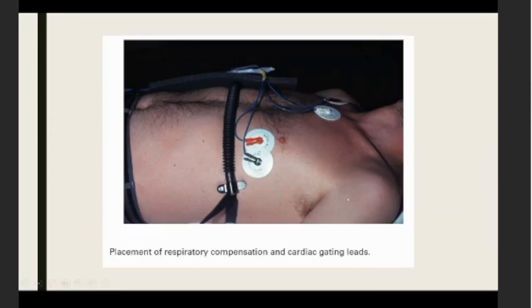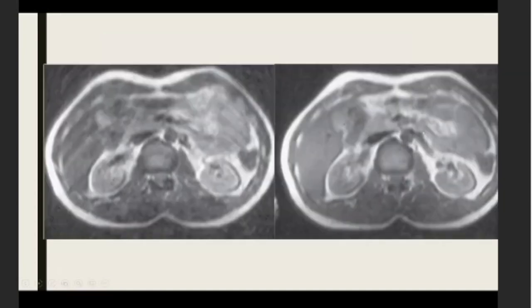As shown in this picture, the trigger line in black is used to define the breath cycle, and here are the cardiac gating leads. On the left side is the image taken without respiratory gating or compensation technique — the ghosting artifact is visible all over the image. On the right side, we used a trigger and respiratory compensation technique, which gives a very good image.